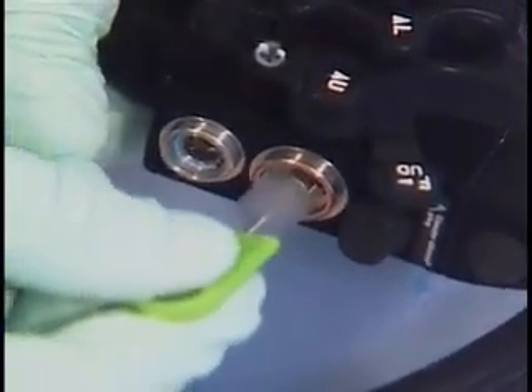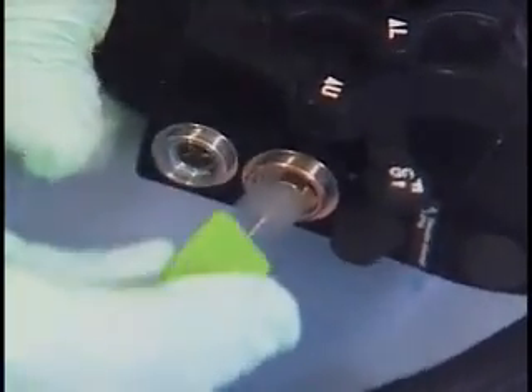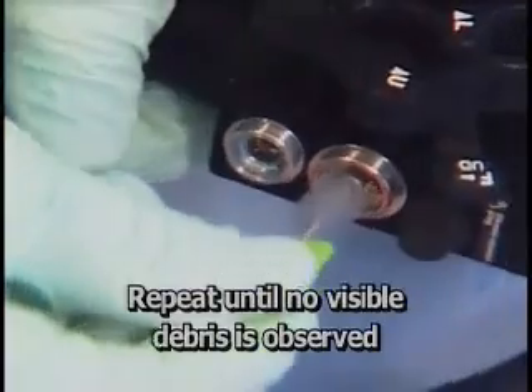The next step is to clean the channel openings. Carefully insert about 1/2 of the channel opening brush into the suction cylinder. Rotate the brush and remove. Clean the bristles. Repeat this process until no visible debris remains. Now, move down to the instrument channel port. Insert the brush. Rotate and remove. Clean the bristles. And repeat until no visible debris remains.